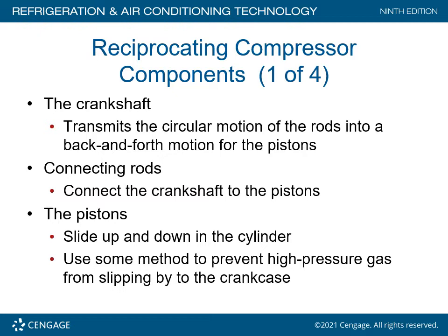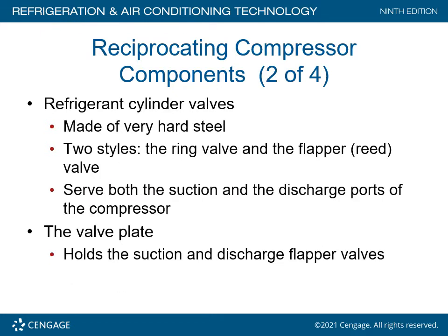Reciprocating compressor components include: the crankshaft, which transmits circular motion of the rods into back-and-forth piston motion; connecting rods, which connect the crankshaft to the piston; and pistons, which slide up and down in the cylinder and use some method to prevent high pressure gas from slipping into the crankcase. Refrigerant cylinder valves are made of very hard steel — two styles: the ring valve and the reed (flapper) valve — serving both suction and discharge ports. The valve plate holds the suction and discharge flapper valves in place.